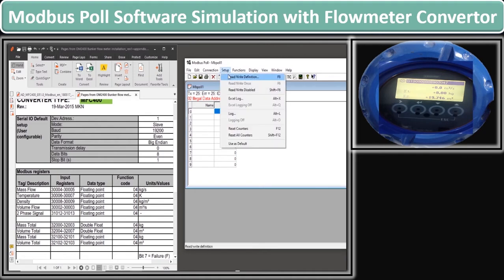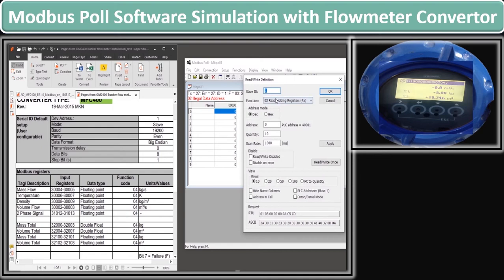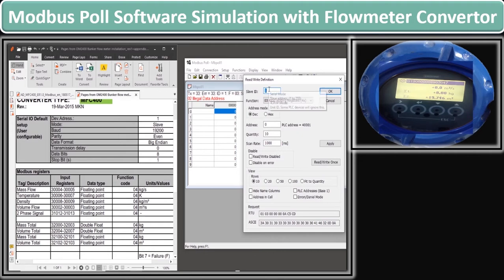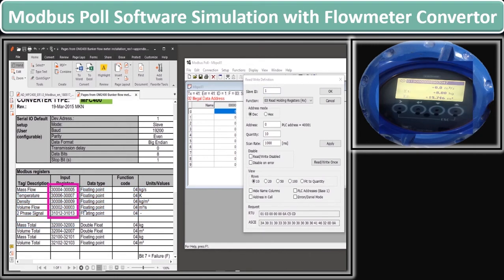Then go to Setup and click on the Read/Write Definition icon to define the Modbus register parameters. The Read/Write Definition window pops up. We have written Slave ID 1 here, as it is defined in the serial parameter section — the device address is given as 1. Now we set the Modbus register parameters and define the input register value. As you can see in the list, it ranges from 30000 to 30013. So we write value 0 in the address section, indicating that our first value starts from 30000.